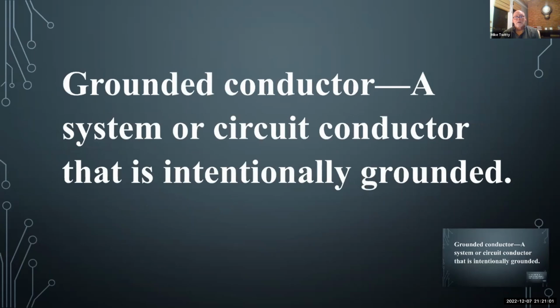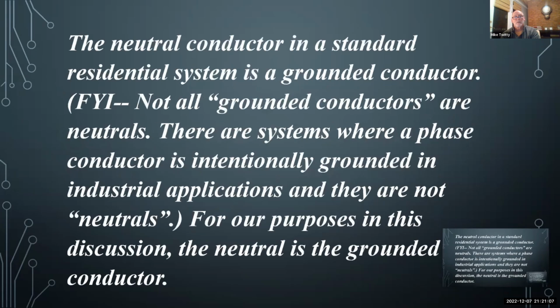Grounded conductor: a system or circuit conductor that is intentionally grounded. Okay, the neutral in a standard residential system is a grounded conductor. Not all grounded conductors are neutrals. That's why the code doesn't just refer generally to all of them as neutrals. They call them grounded conductors.